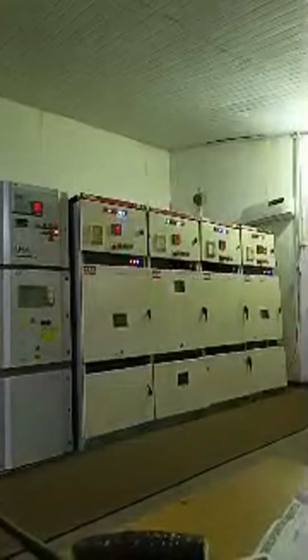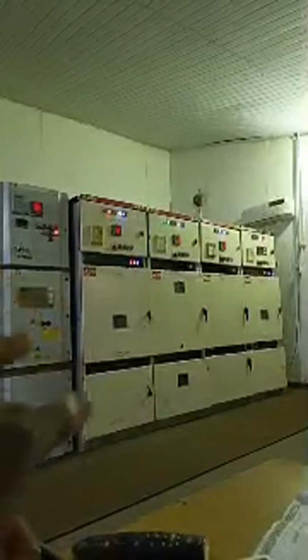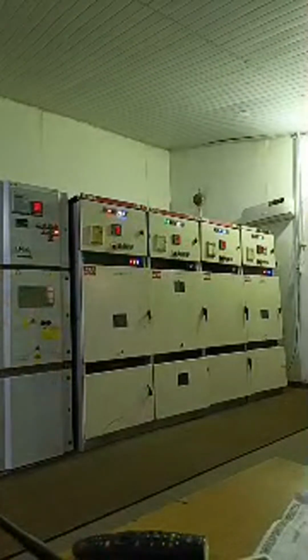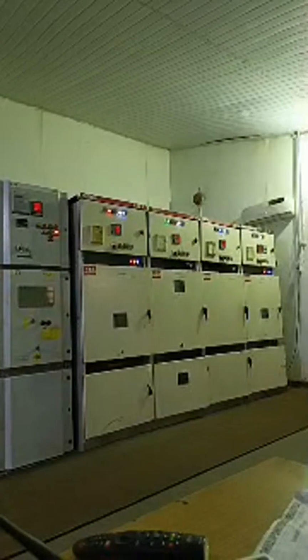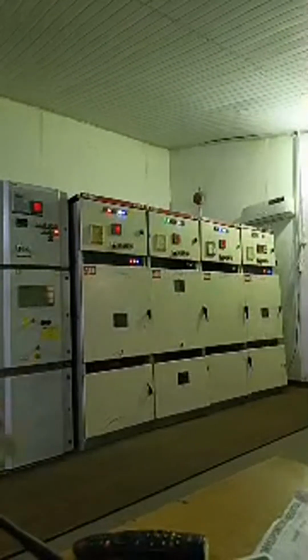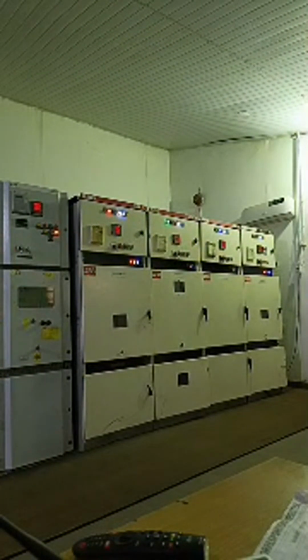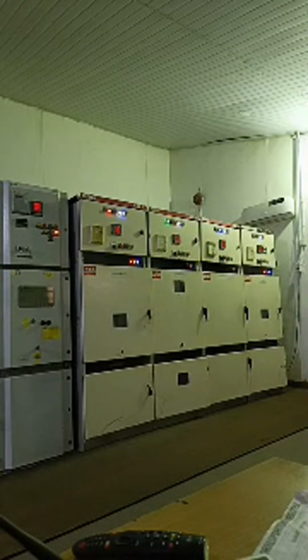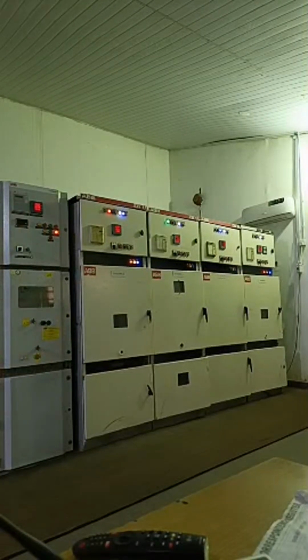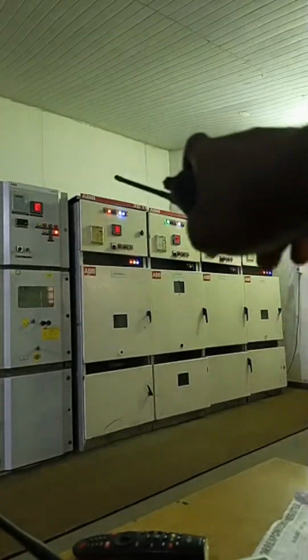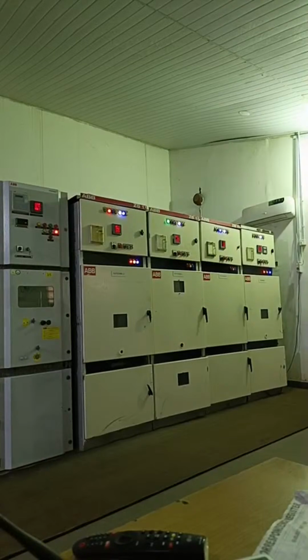The voltage transformer steps down this light. You see there's an indicator light, all this on, off indicator light, 11 kV display on the screen. The advantage of the VT, which is the voltage transformer, is converting the voltage to step down to the voltage that is able to make this display light work, because the 11 kV cannot work on those tiny bulbs. So 11,000 volts cannot work on those tiny lights. So the help of the VT, the voltage transformer, is to step down for those lights to be able to work. That's the help of the VT.